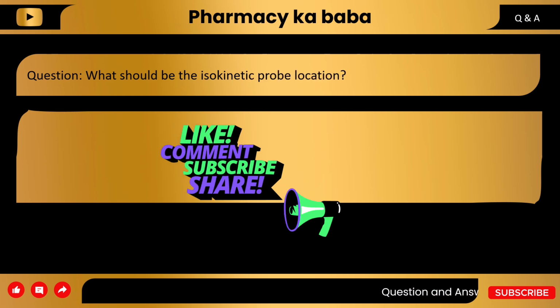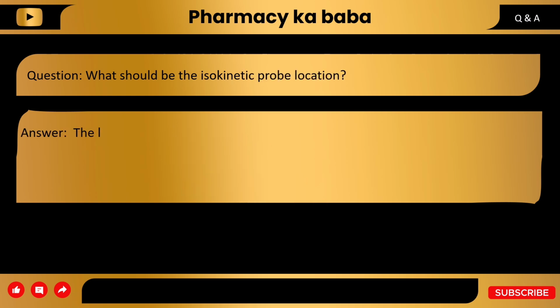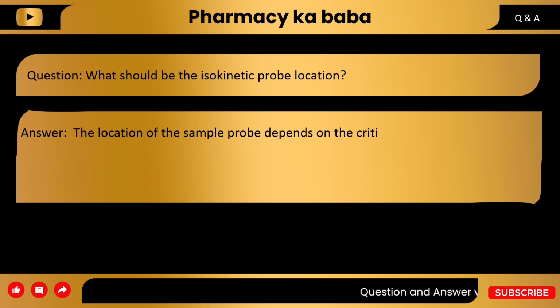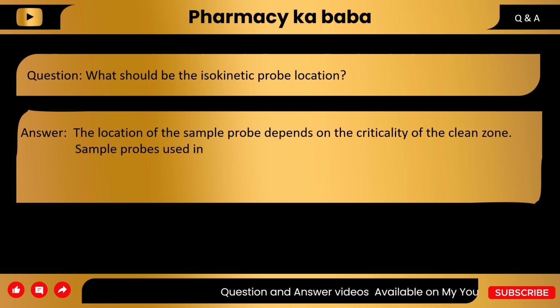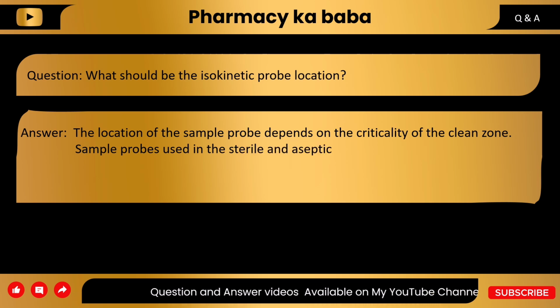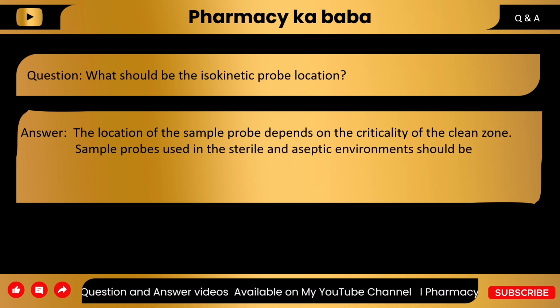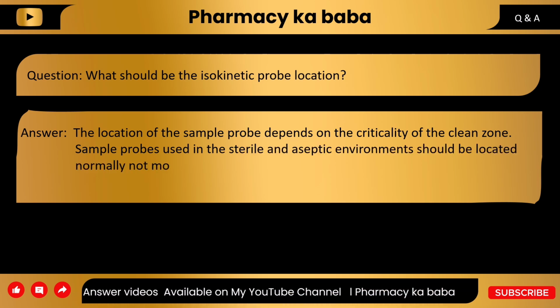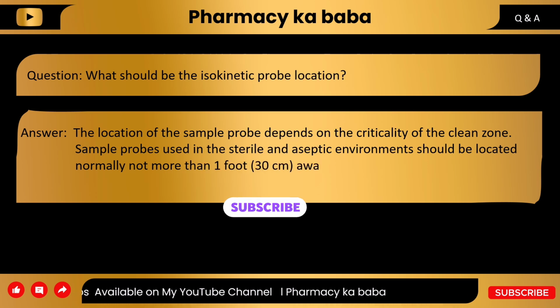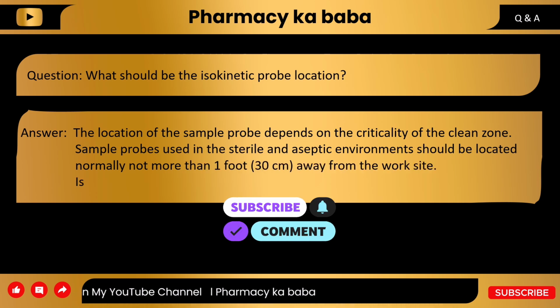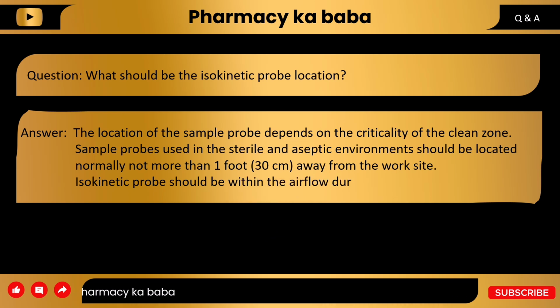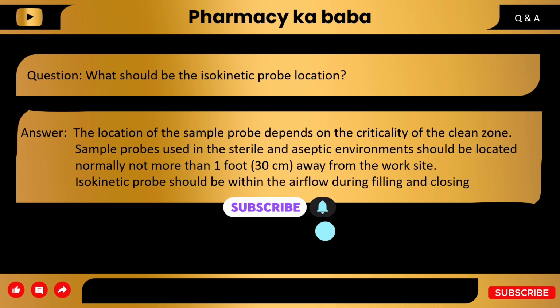Question. What should be the isokinetic probe location? Answer. The location of the sampling probe depends upon the criticality of the zone. A sample probe used in a sterile and aseptic environment should normally be located not more than 1 foot away from the working site. The isokinetic probe should be within the airflow during filling and closing operations.